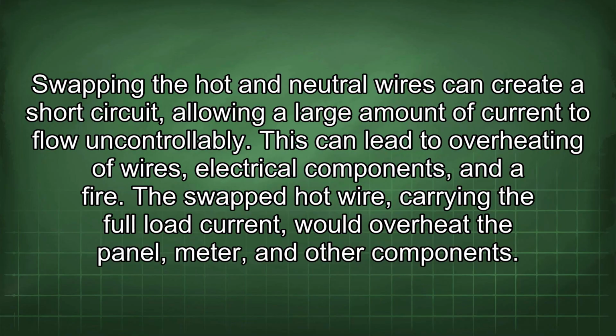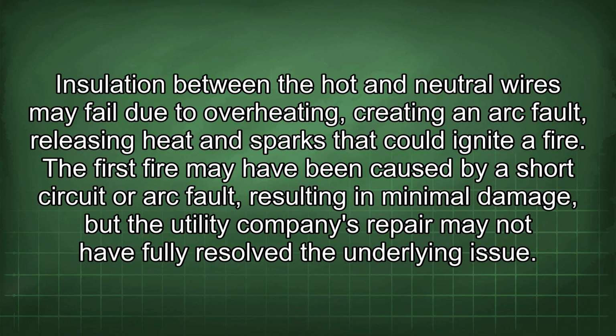Swapping the hot and neutral wires can create a short circuit, allowing a large amount of current to flow uncontrollably. This can lead to overheating of wires, electrical components, and a fire. The swapped hot wire, carrying the full load current, would overheat the panel, meter, and other components. Insulation between the hot and neutral wires may fail due to overheating, creating an arc fault, releasing heat and sparks that could ignite a fire.